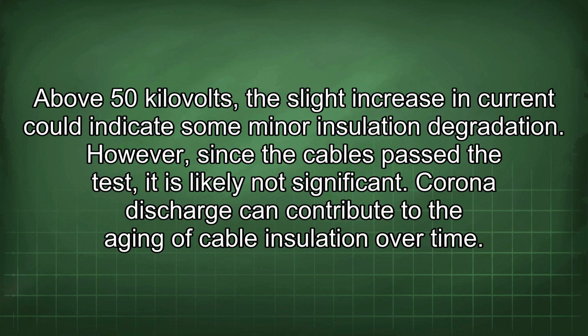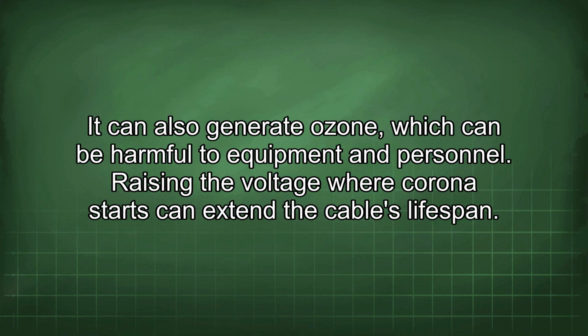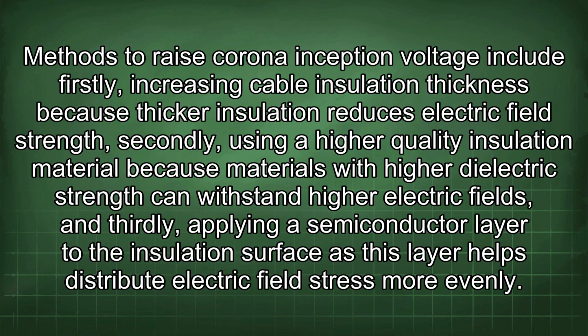Corona discharge can contribute to the aging of cable insulation over time. It can also generate ozone, which can be harmful to equipment and personnel. Raising the voltage where corona starts can extend the cable's lifespan. Methods to raise corona inception voltage include, firstly, increasing cable insulation thickness, because thicker insulation reduces electric field strength. Secondly, using a higher quality insulation material, because materials with higher dielectric strength can withstand higher electric fields. And thirdly, applying a semiconductor layer to the insulation surface, as this layer helps distribute electric field stress more evenly.